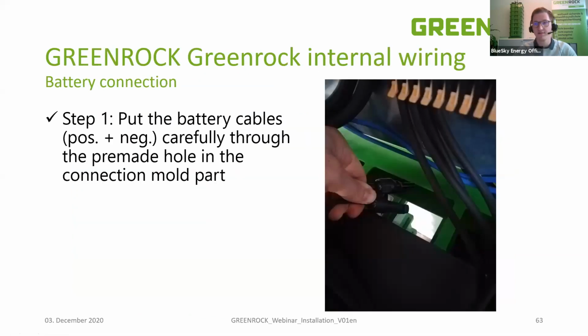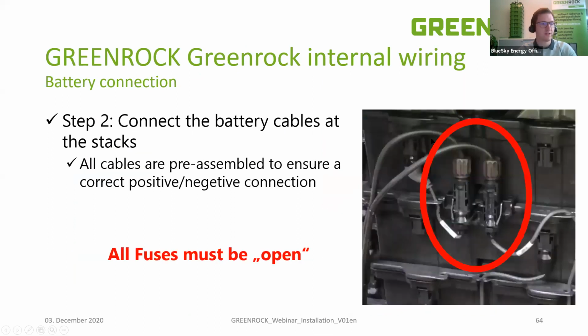So then we're already done with the combination of 2 boxes. Then we can already wire the battery cables. These are just pushed through the housing inside the stack, so you can just connect plus and minus. Please, before connecting, the fuses must be opened.